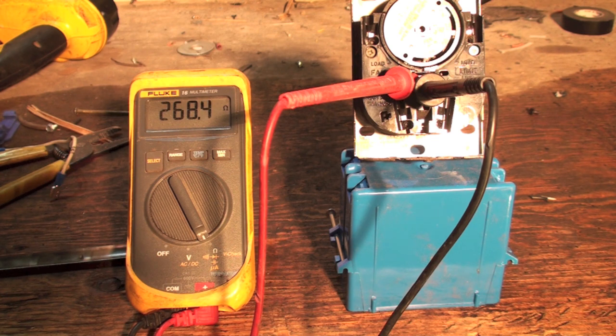And that heater simply warms the bimetal up a little bit so it won't do that. This is a short cycle issue. It's not the worst thing that can happen to your furnace, but it does affect the operation of the furnace.